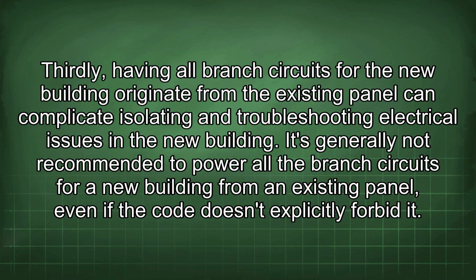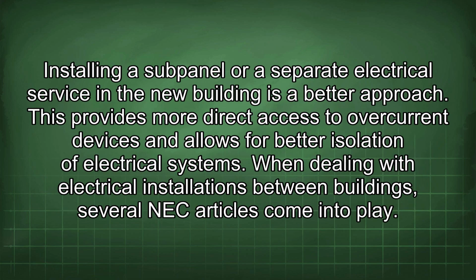It's generally not recommended to power all the branch circuits for a new building from an existing panel, even if the code doesn't explicitly forbid it. Installing a sub-panel or a separate electrical service in the new building is a better approach. This provides more direct access to overcurrent devices and allows for better isolation of electrical systems.